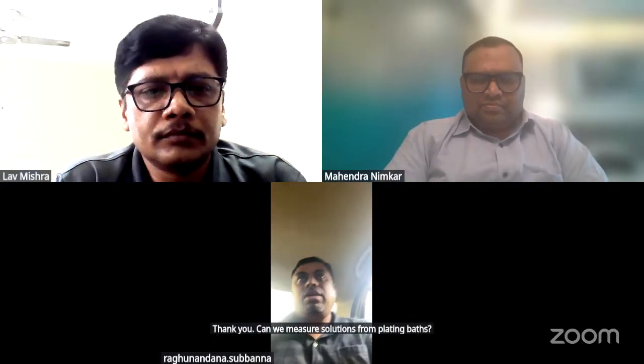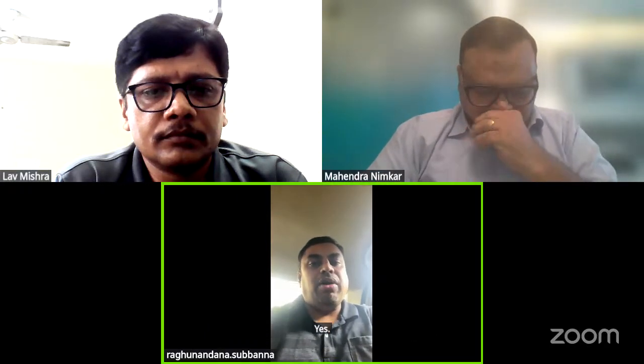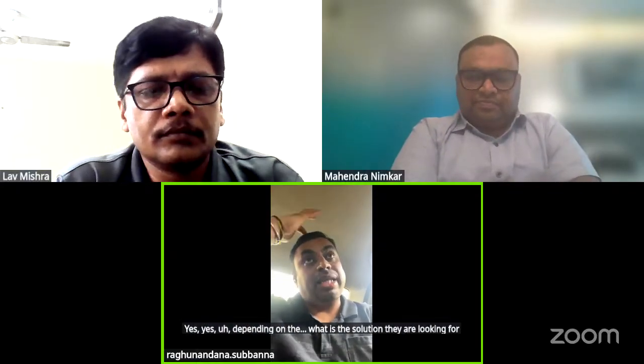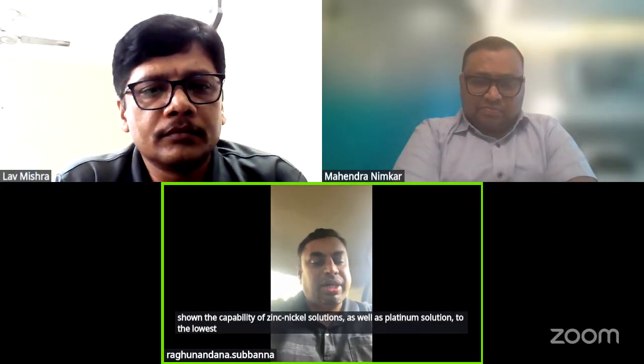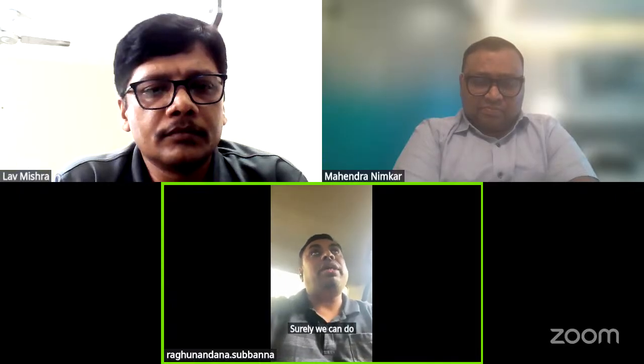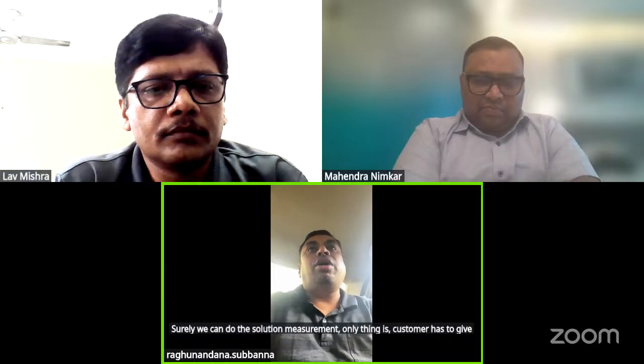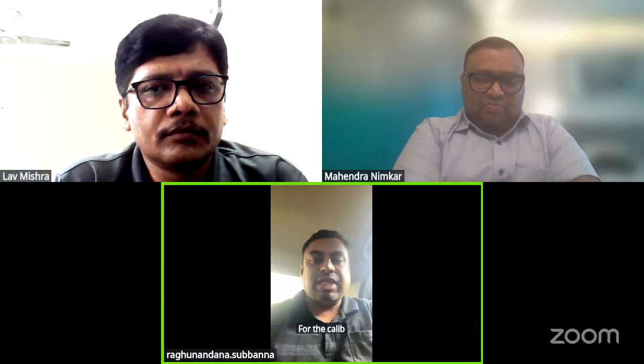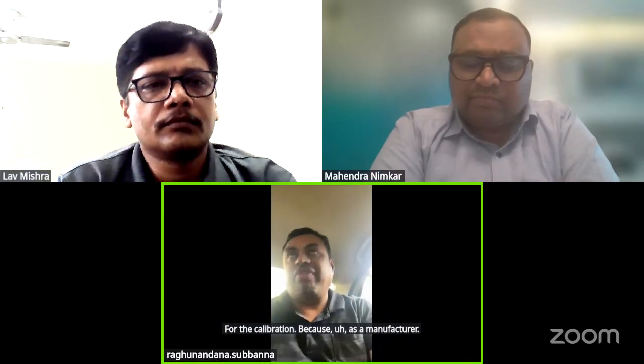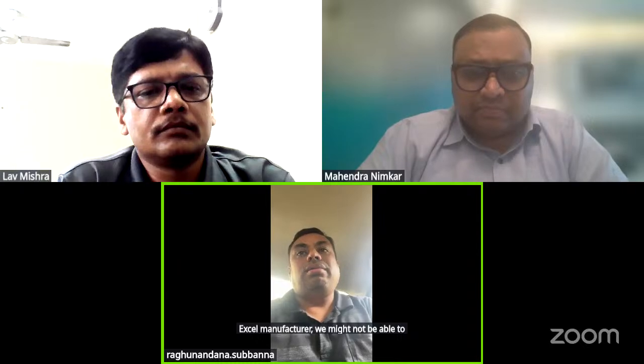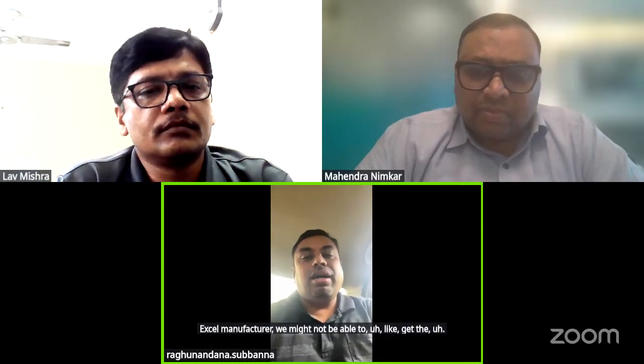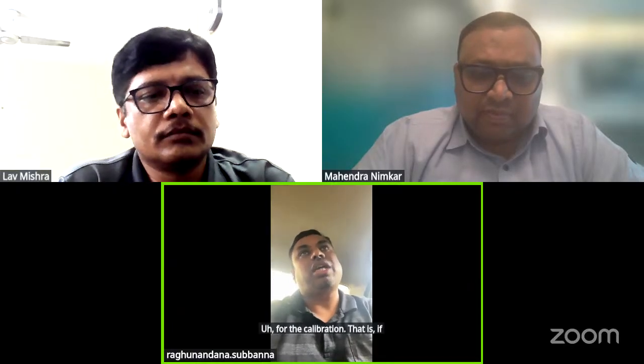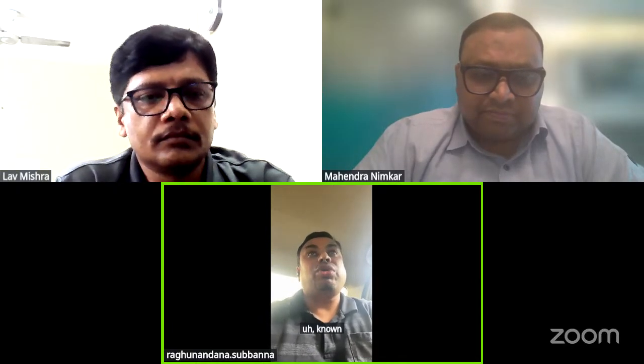Thank you. Can we measure solutions from plating baths? Yes, depending on what solution they are looking for. Mahendra has already shown the capability for zinc nickel solutions as well as platinum solution, where we have measured down to ppm levels. Surely we can do the solution measurement. The only thing is the customer has to give us known samples for calibration, because as an XRF manufacturer we might not be able to get the samples. If the customer gives us known samples, then we can surely calibrate the instrument.